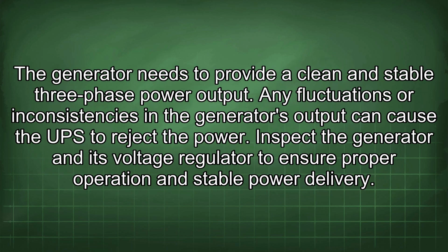Fourthly, generator output should be verified. The generator needs to provide a clean and stable three-phase power output. Any fluctuations or inconsistencies in the generator's output can cause the UPS to reject the power. Inspect the generator and its voltage regulator to ensure proper operation and stable power delivery.